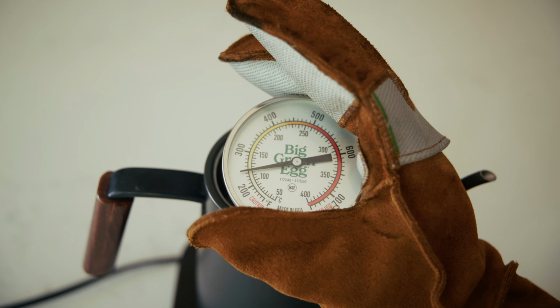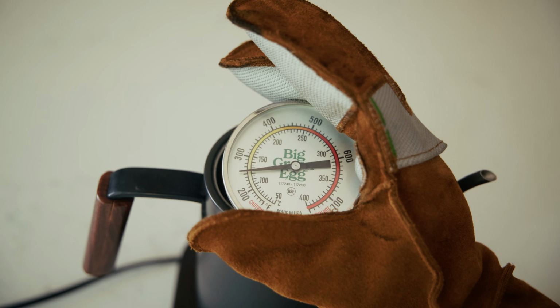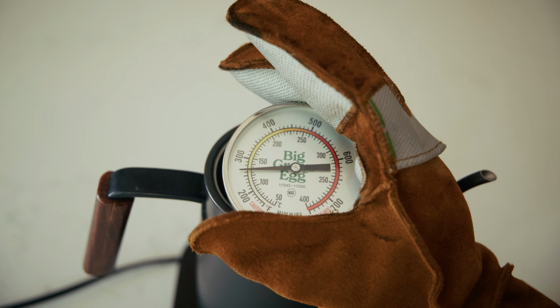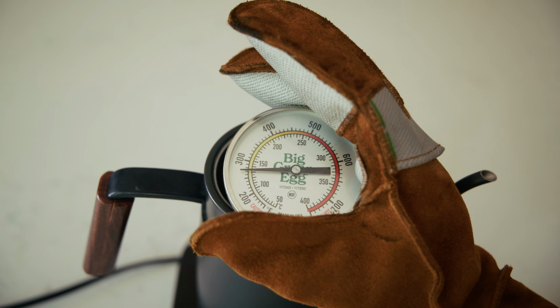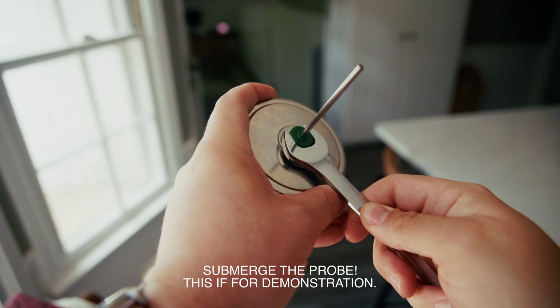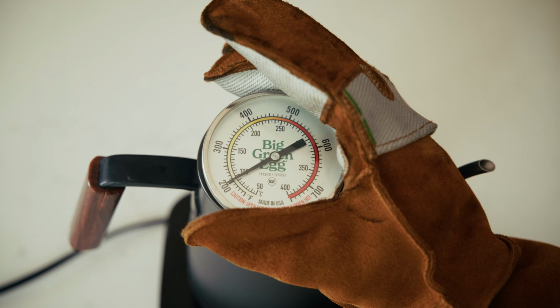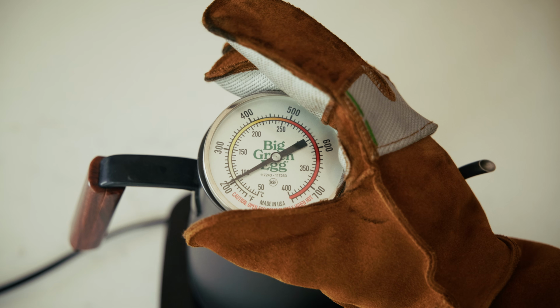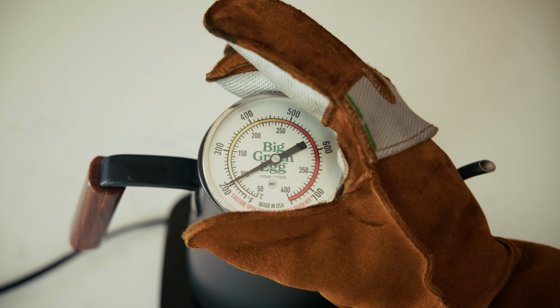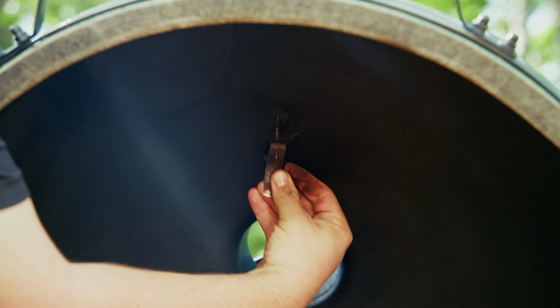Anyways, submerge the probe of the thermometer in the boiling water and be careful not to touch the bottom or the sides of the pot. That could interfere with the reading. You guessed it, if the thermometer says anything other than the boiling temperature, it needs a calibration. While the probe is still submerged, use a 5/8 inch wrench to gently turn the hex nut on the back of the thermometer until the dial reads the boiling point temperature. Once calibrated, reinstall the thermometer in the dome.